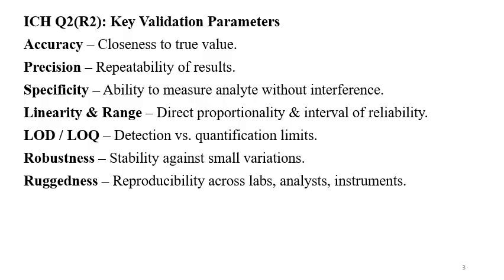Accuracy means the closeness to the true value. Precision is the repeatability of results. Specificity means the ability to measure the analyte without interference. Linearity and range refer to direct proportionality and the interval of reliability. LOD and LOQ represent detection versus quantitation limits.